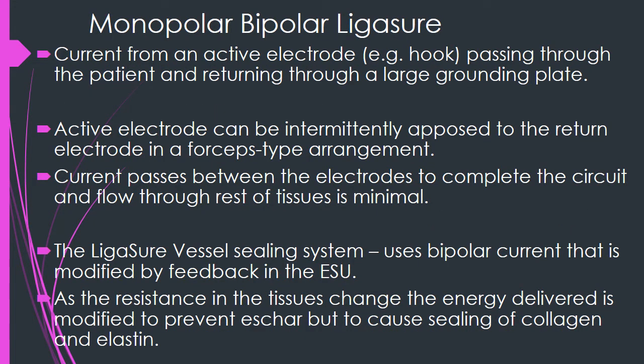While using monopolar cautery, there is only one active pole which is touching the patient; the other pole is the grounding electrode. In bipolar cautery, the active electrode is intermittently opposed to the return electrode in a forceps-type arrangement, so the current passes between the two electrodes to complete the circuit. Thus the flow through the remaining tissues of the rest of the body is very minimal.